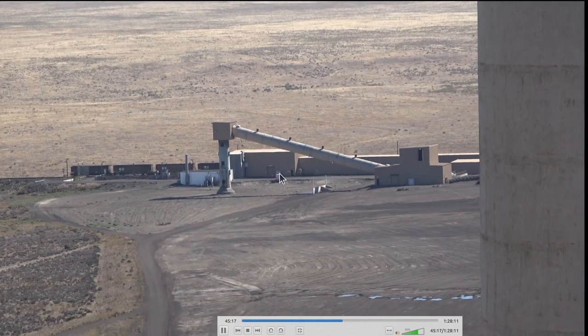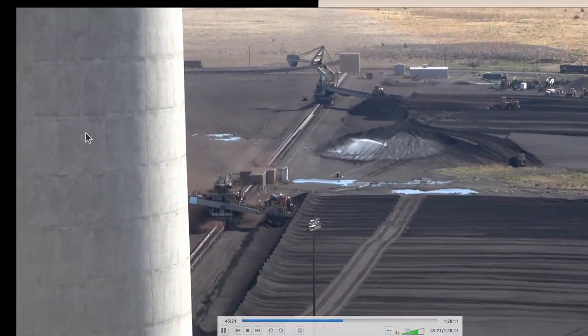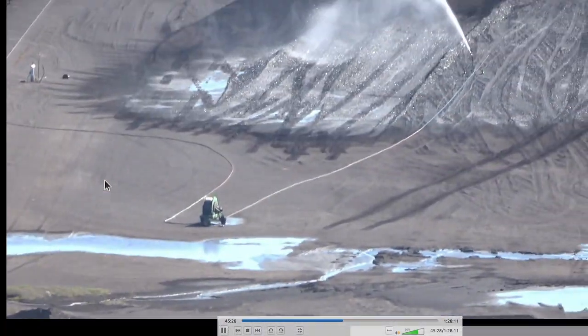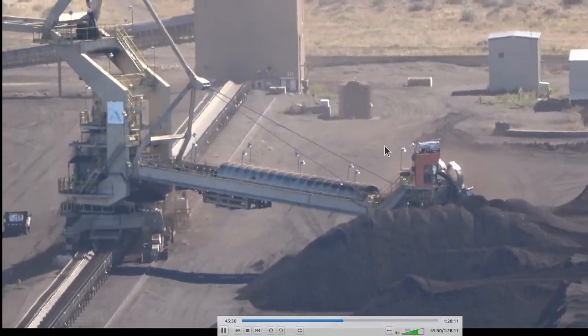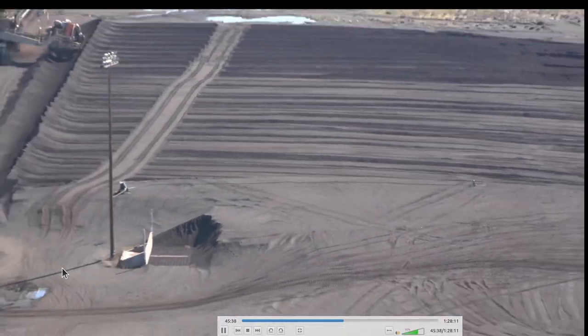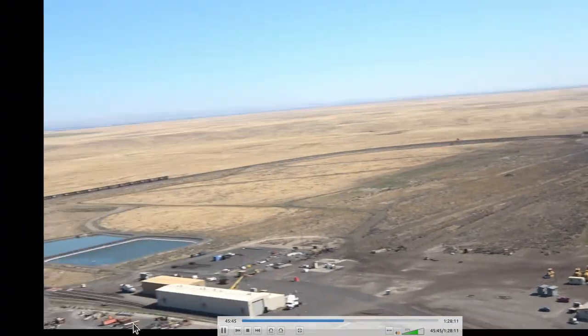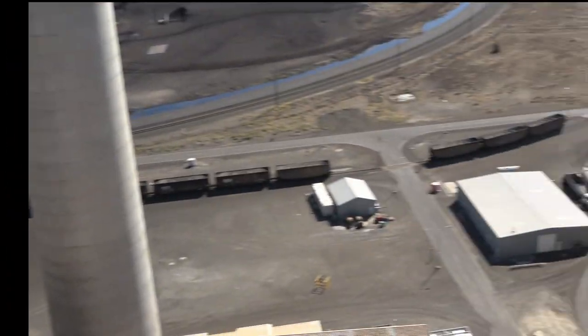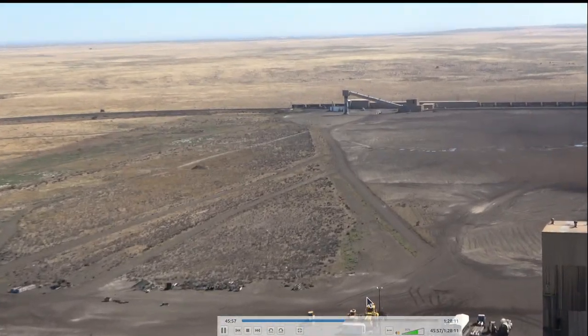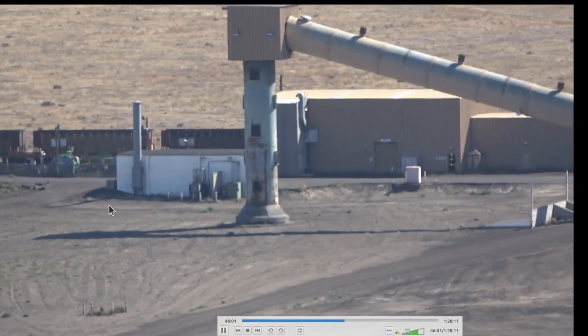That's the dumper building out here — here's a lowering well where any excess coal can be dumped. This is on day shift just running the number three. There's an emergency feed here — if you lose both of your reclaimer stackers you can push coal in and feed it. All the rail cars are aluminum cars so they carry more weight and they have rotating couplers on them. The clamps grab the top and roll the car over, and everything dumps out the top. It takes about 180 seconds to dump a car — around 100 tons of coal.